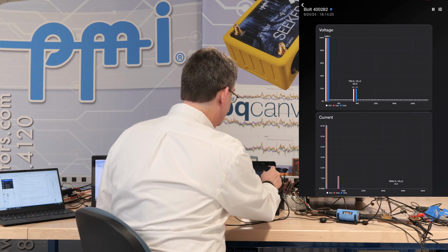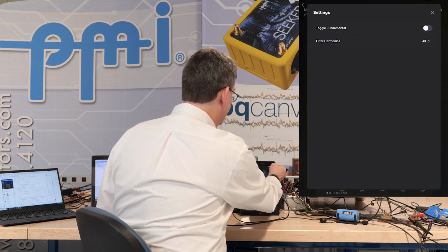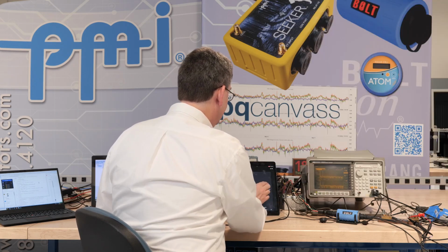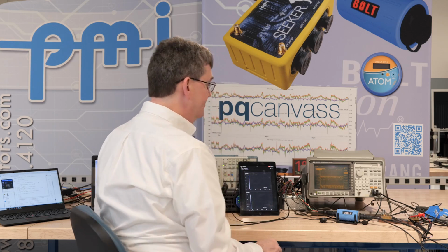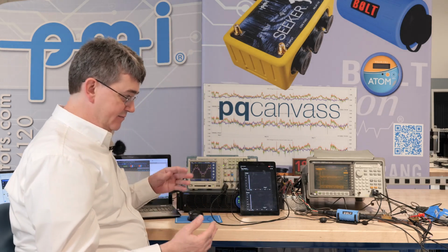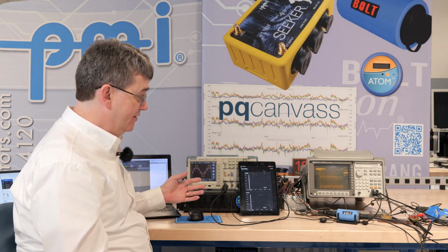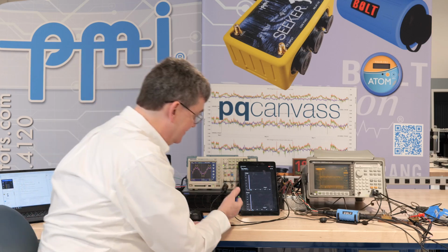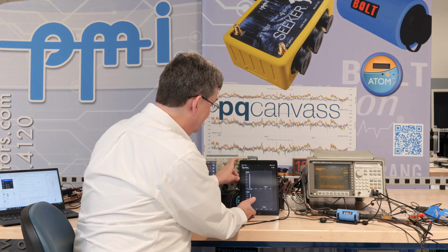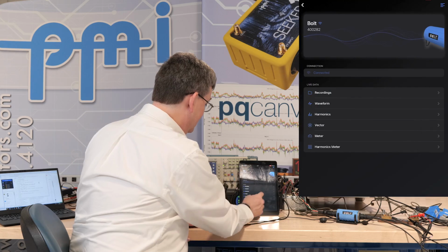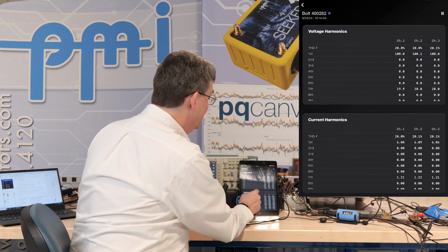Let's turn off the fundamental to make sure there are no other frequencies present. So the two-tone test will produce other frequencies, sums and differences of 60 Hertz and 420 Hertz, that would manifest themselves here as other harmonics. But we see these levels are all close to 0. We can look at the meter display to verify that.